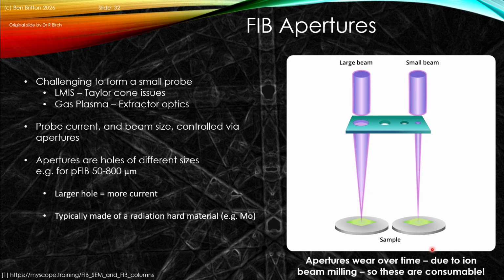Now, one of the key things here in that process is that the ion beam and selecting the appropriate probe current is typically performed with an aperture. This is because it's relatively challenging to form a relatively small probe. This is related to how the Taylor cone forms and the extractor optics in the gas plasma systems. So what you tend to do is you use apertures of a series of different sizes that will control the probe current and beam size, where you can deflect the beam across different holes in a so-called aperture strip. And then once you've done that and you've used the focusing optics afterwards, you draw that onto the sample.